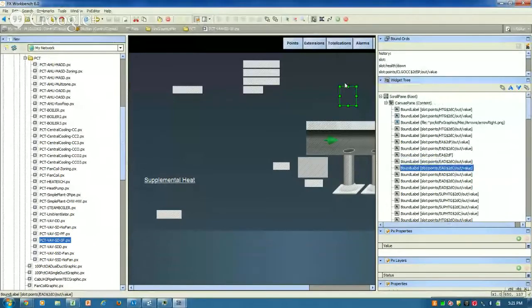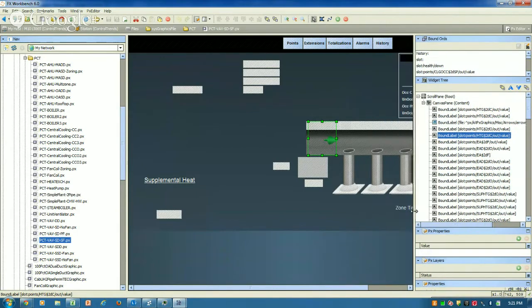So in here, all the graphics are populated with every single image you could possibly have. If you have a different controller that doesn't have a point known as heating-C, you can change the name of your controller's point to heating-C, or change this to whatever the name of your point is, and it'll automatically populate that in a graphical image, or automatically put the value on the screen.